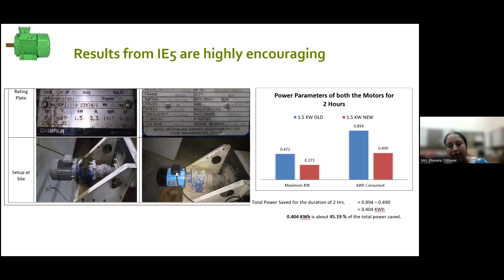Here we can see that a 2.2 kilowatt motor was replaced by a 1.5 kilowatt motor. We targeted a lower size motor because the same expected output can be achieved using an energy efficient motor. Since we are going for an energy efficient motor, we can achieve the same result with a smaller size, reducing capital investment too. Here you can clearly see the savings achieved of around 29.31%.